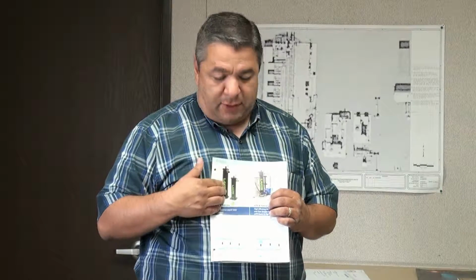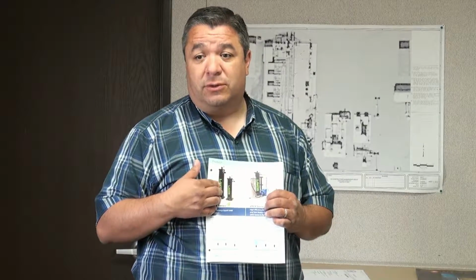So it really is a nice system for towers, for cooling towers. Now they also have other applications, side stream applications, where they take water out of the main header before it gets to the chiller. They take about 10-15% out, clean it, send it back. So those are different applications.